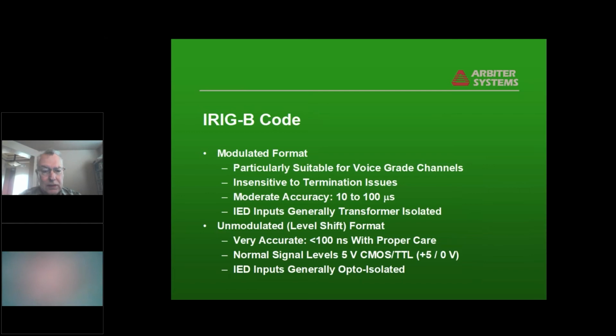The IRIG code, as I mentioned, is designed to be transmitted over voice grade channels like instrumentation tape recorders and telemetry systems. It's because it's basically a narrow band, low frequency signal. It's very easy to transmit. Terminating the transmission lines that we'll talk about in a little while is not really much of an issue. You can run it over any twisted pair telephone type line. And the IED inputs generally have, as they would on a modem, a transformer isolation. And you can get accuracy of 10 to 100 microseconds. And for some things, that's perfectly good enough.